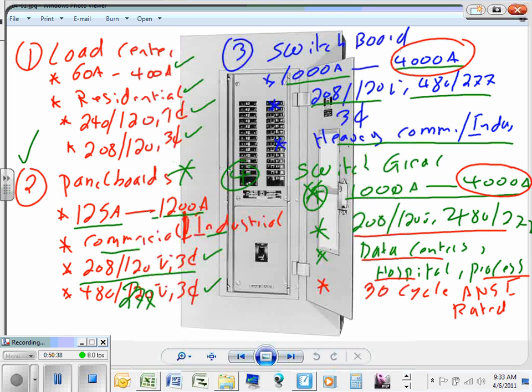Why? Because they make the switchgear to ANSI standards, and with ANSI standards they insulate everything. They have 3 chambers. The key point for switchgear: 3 chambers, each completely isolated from the others. Chamber 1 is for the circuit breaker, chamber 2 for the buses going up and down, and chamber 3, guys, for cables. From the bottom, you can bring all your cables and feed the buses from the back of the switchgear. You're talking about close to 72-inch deep switchgear, so these are bigger equipment.